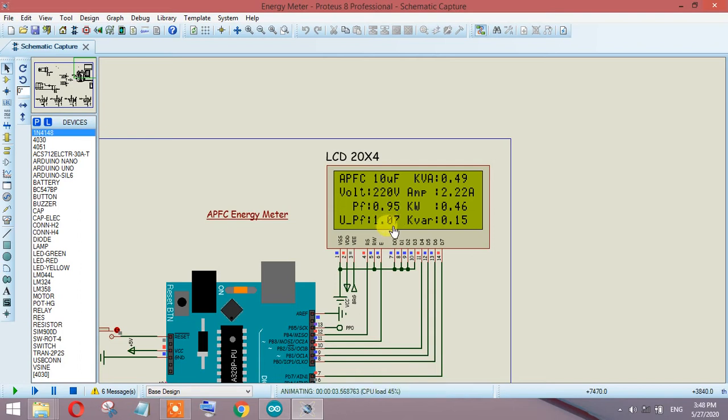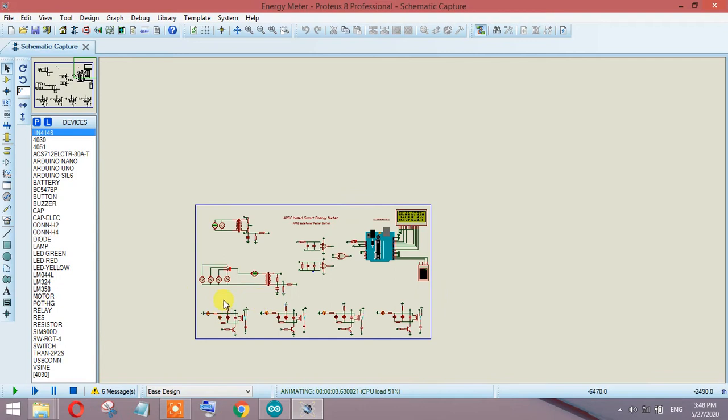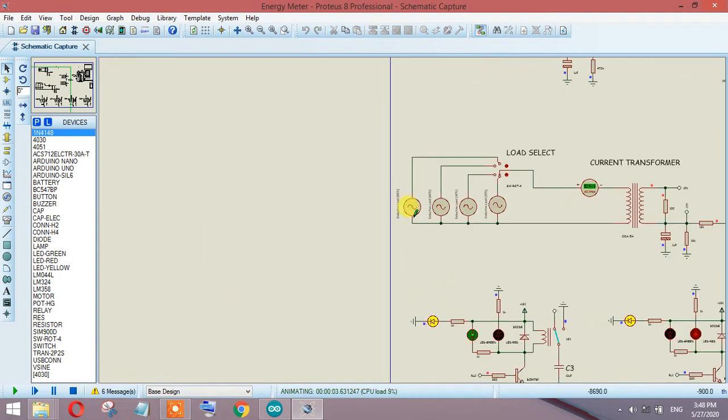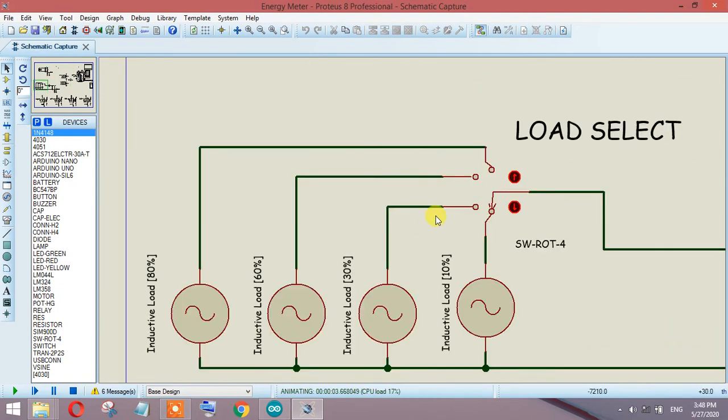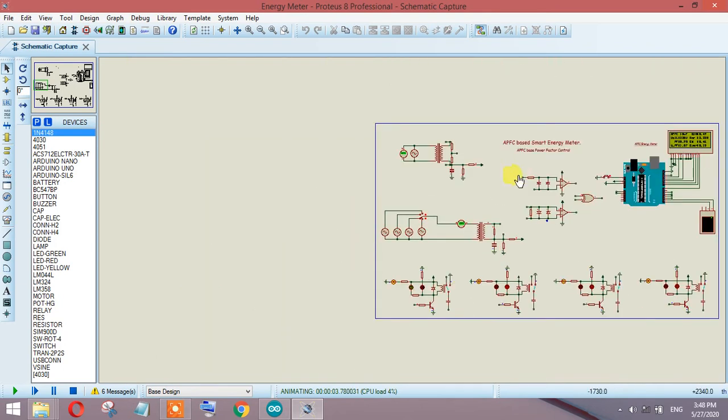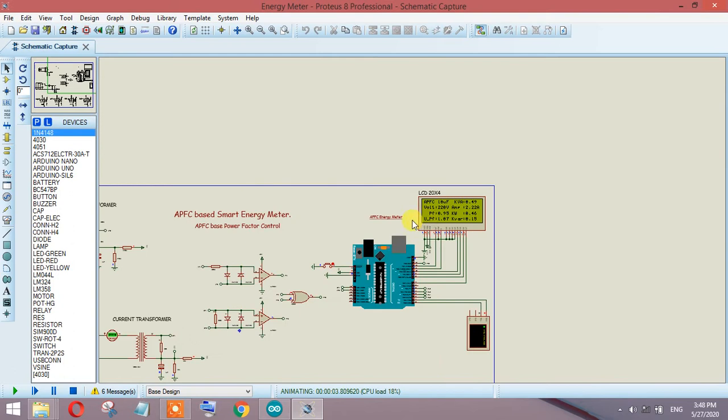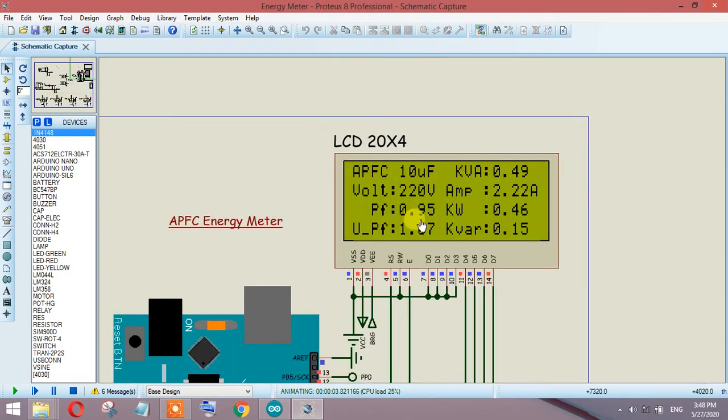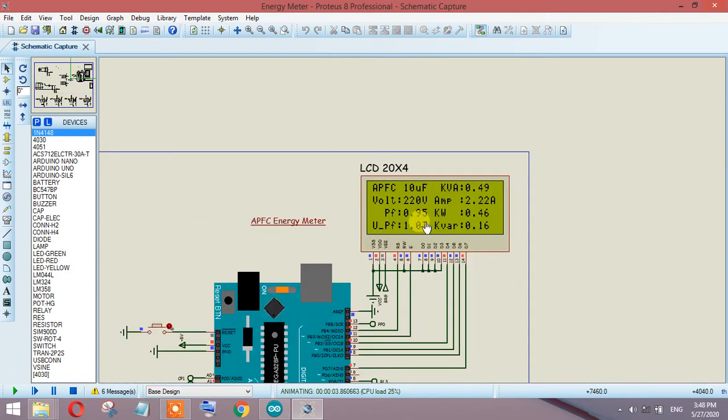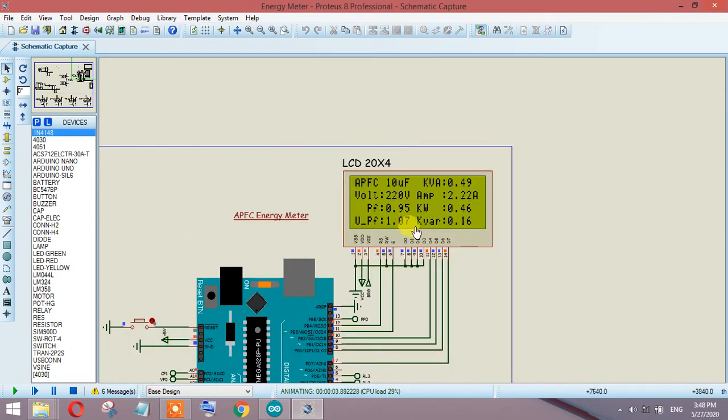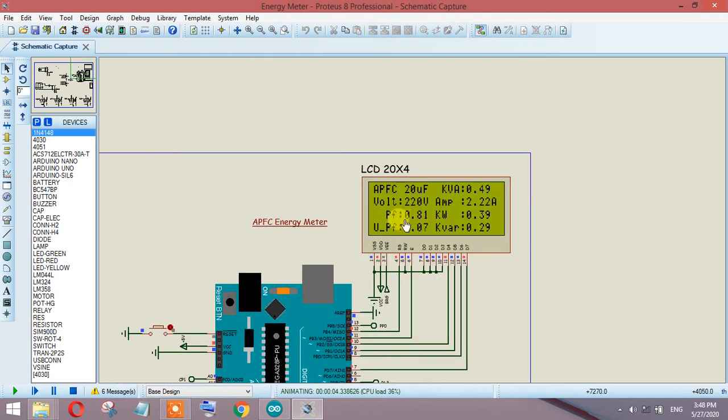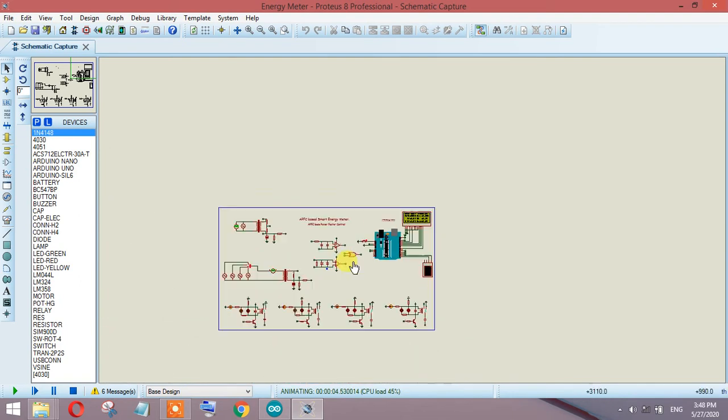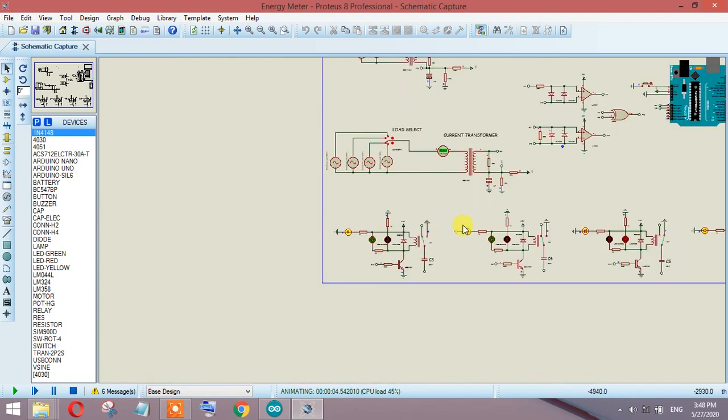Let's add more inductive load and jump to 30% inductive load. The values will be changing, it will take a little bit of time to update. Right now the power factor dropped to 0.81 and the updated power factor moved to 1.03.